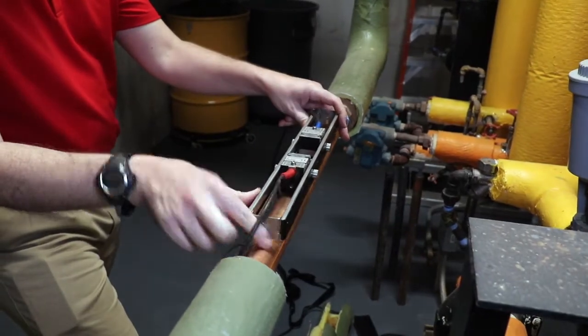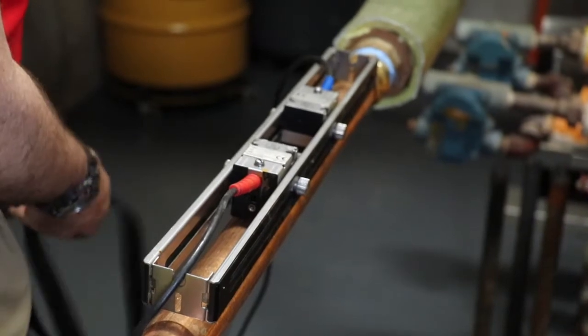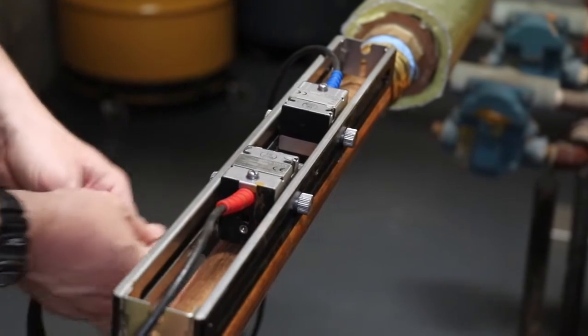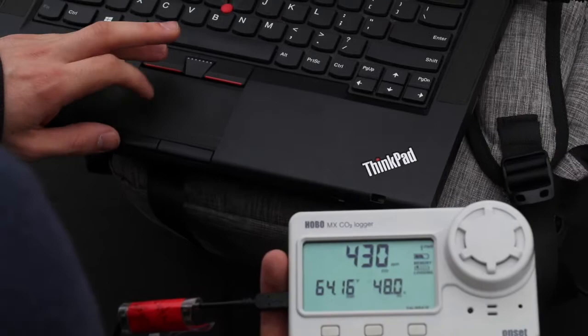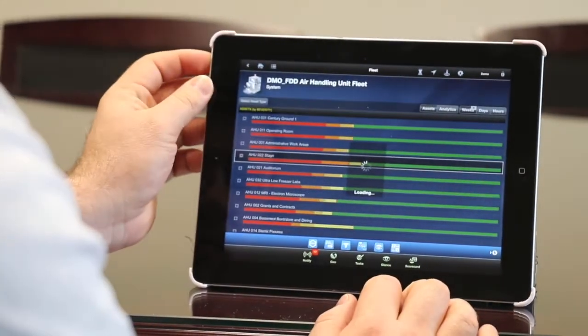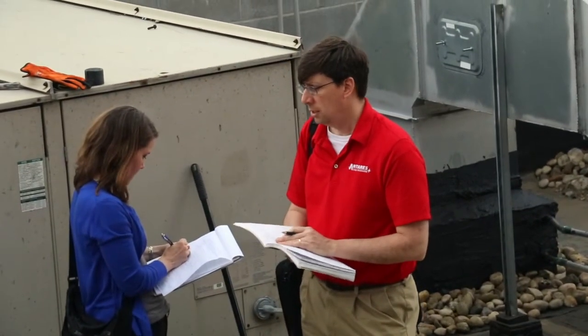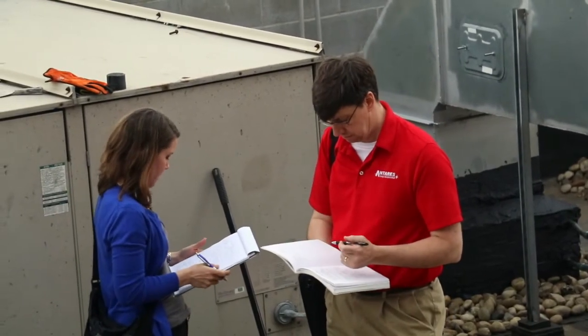There's going to be a lot of on-site work at the beginning, doing ASHRAE Level 2 audits, taking as-used energy consumption profiles and patterns from both your EMS systems, plus doing some spot data logging using various strategies of CTs and data loggers, ultrasonic flow meters, occupancy sensors, CO2 sensors, and other methods to understand how energy is being used and where the opportunities are for St. John's University to improve their energy efficiency.